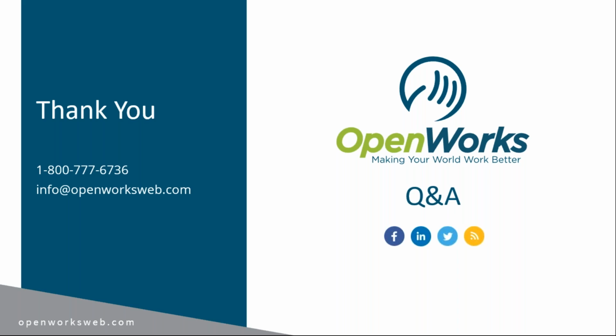Thanks, Brian. Filters typically being changed quarterly is best. If you're increasing your MERV rating, that means that you're going to be collecting more dust on those filters, and they're actually going to need to be replaced more often. So you might go to monthly or every other month. That's going to be your best practice.